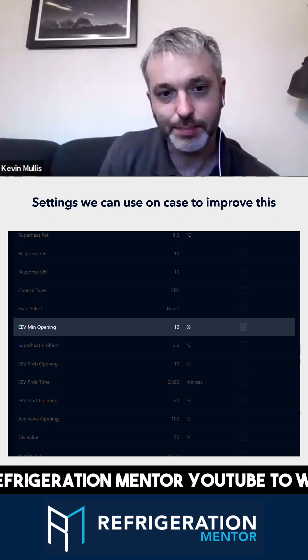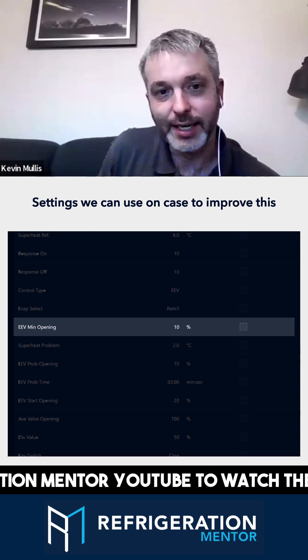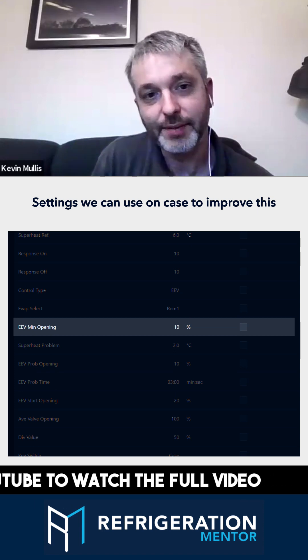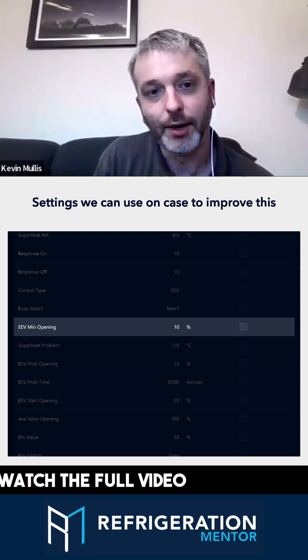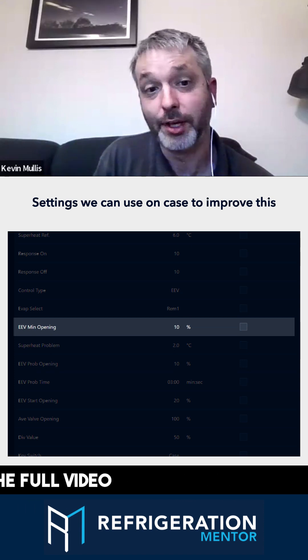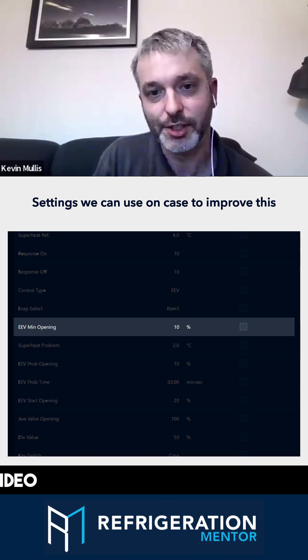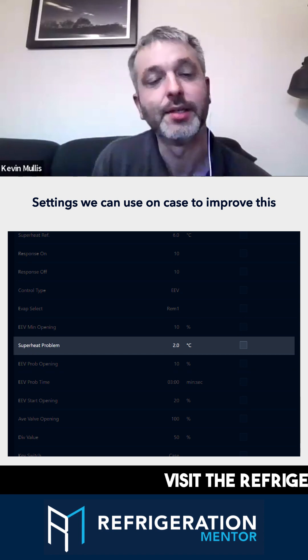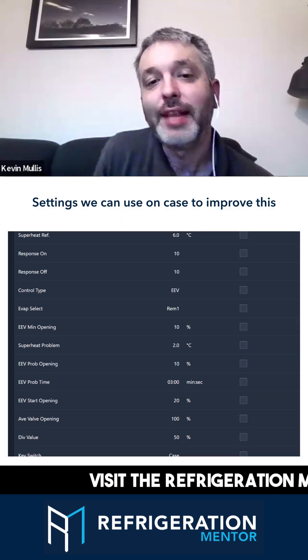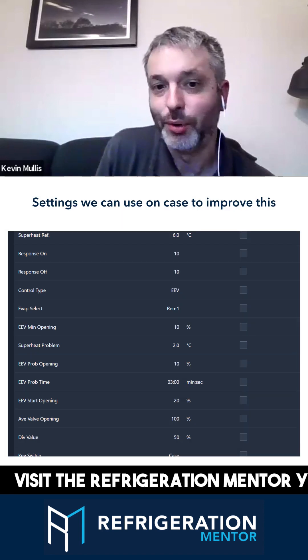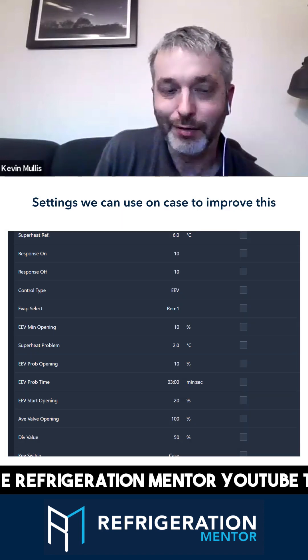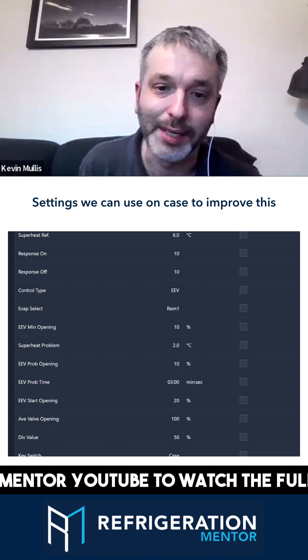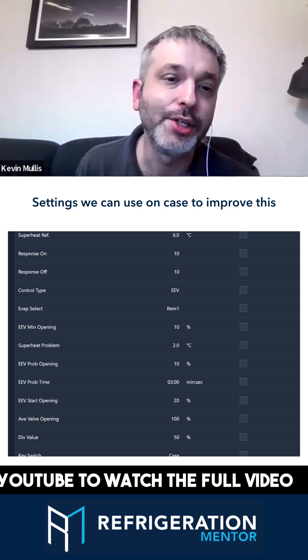As you can see on this, my problem opening and my minimum opening for the EEV are quite low. They're not zero, but they're quite low. And the superheat problem is two degrees. That's to make sure that the valve does shut down a bit if the superheat gets too low.